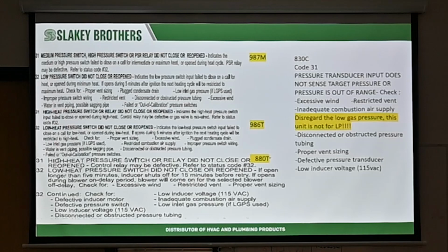See this little section here, which is the 987M. This little section for the 986 and the 880T are pretty much the exact same thing. Simple and to the point. If your flue is good, always confirm your flue is good. Confirm that no water is getting into the inducer motor. You'll hear a little bit of splashing sometimes, because as a collector box cools off or as the inducer motor cools off, a little bit of moisture is in there.